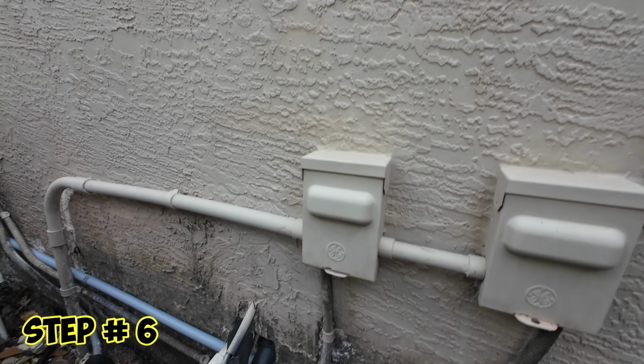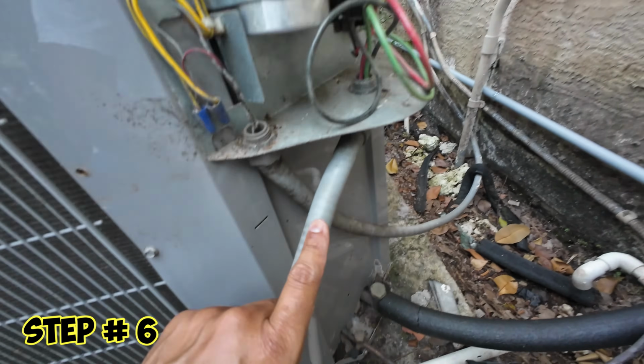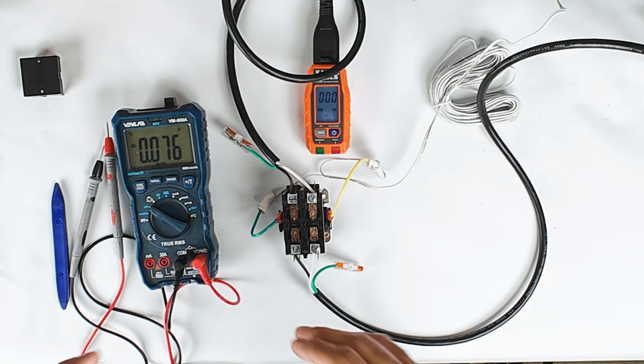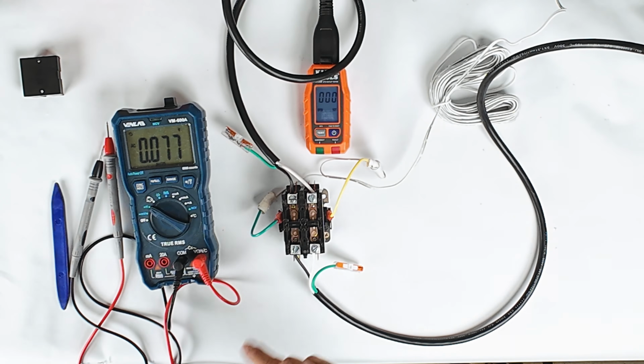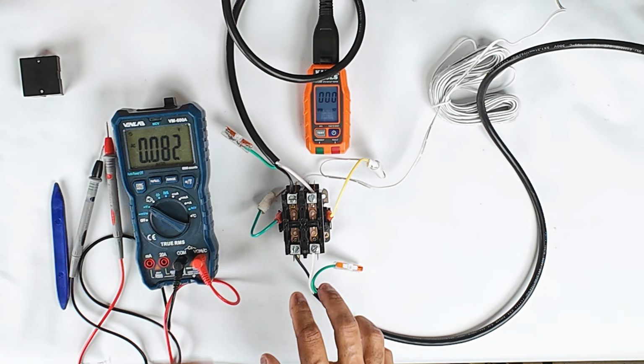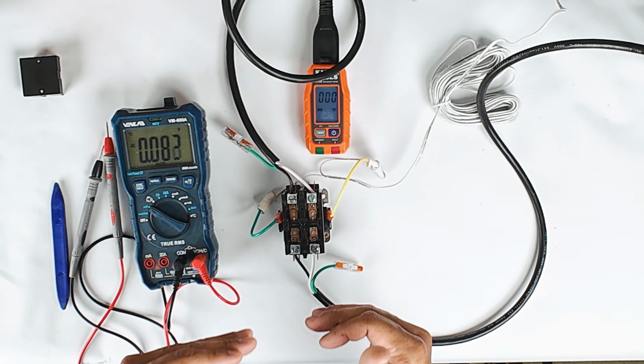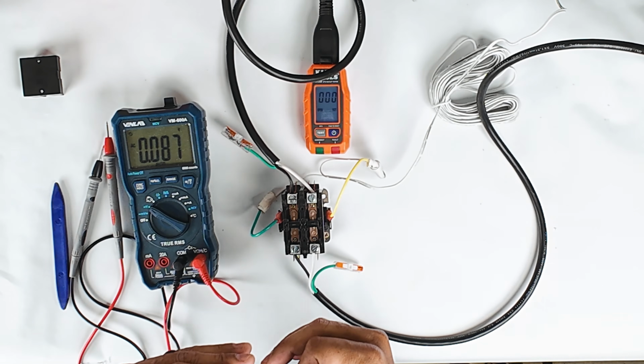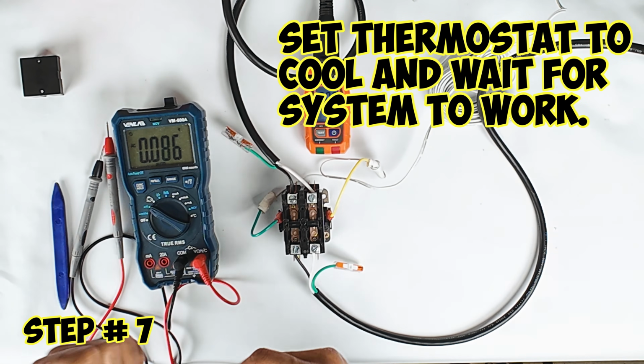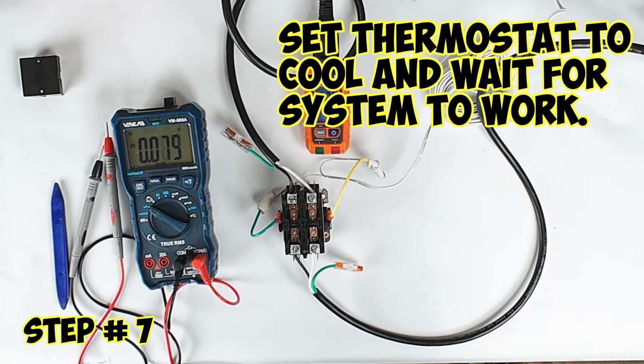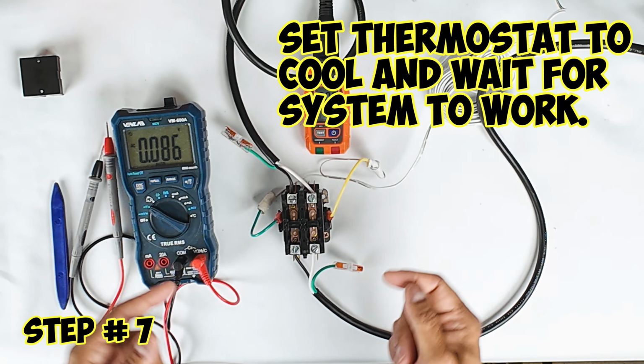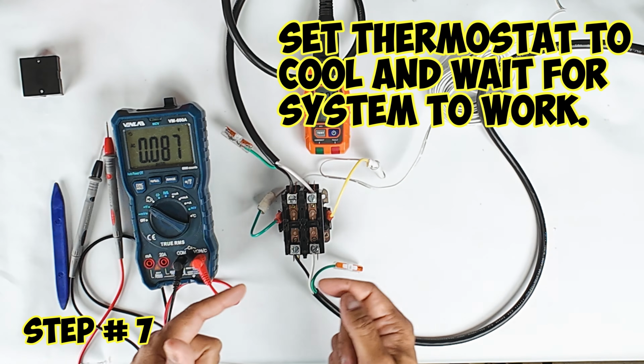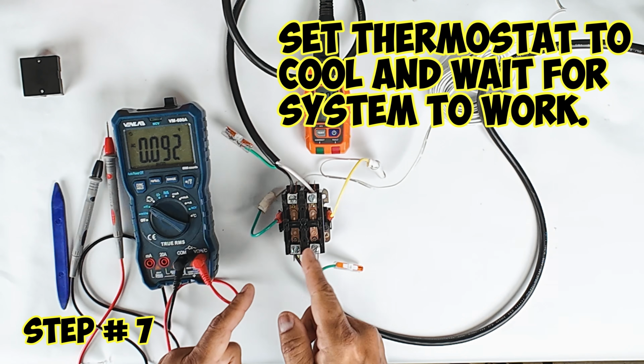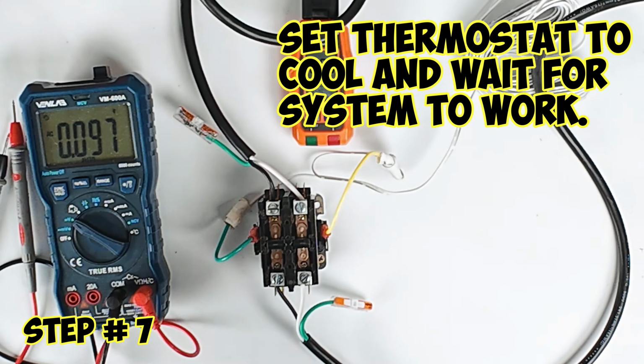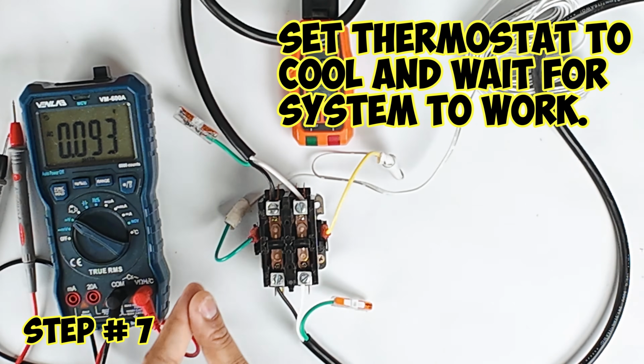Step 6, you want to go ahead, turn on your breaker or your disconnect or whatever it is, and you can measure the incoming voltage. If you have incoming voltage, then you know that the contactor is ready to go once it's called for cooling. The last step is turn on your thermostat to cool or heating or whatever it is, and you should be good to go. You can listen to it and wait for it to be energized and watch to make sure that your contactor is energized and it sends power to your compressor or your fan motor.